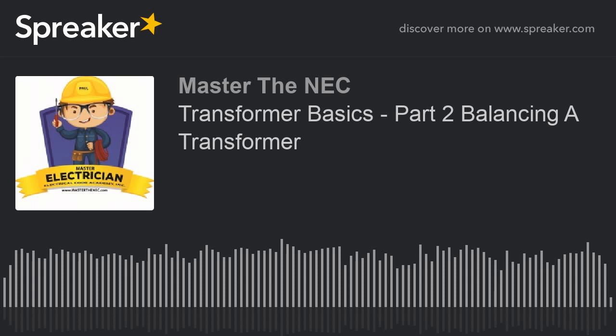Well, in this case, I probably would choose a 90 kVA transformer, because I need to make sure that one of the windings, especially phase A, is going to at least be able to handle the 28 that is being imposed on it, because that's what we designed it at. So I'm going to probably use a 90 kVA, and I've got some room there for some capacity. And I have to balance that out.